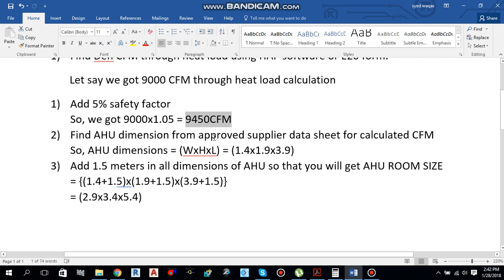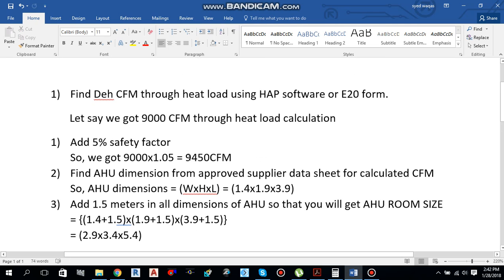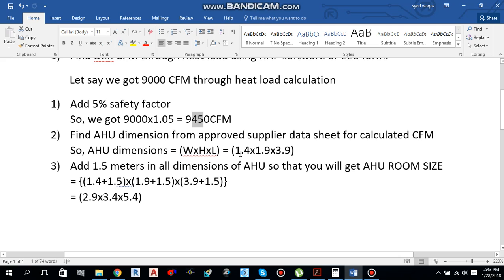As you can see, the AHU selected from the approved supply data sheet for our calculated CFM of 9450 CFM has width 1.4 m, height 1.9 m, and length 3.9 m. If we add 1.5 meters to all dimensions of the air handling unit, we get the room size. Adding 1.5 m to the width, 1.5 m to the height, and 1.5 m to the length gives us a total AHU room size of: width 2.9 m, height 3.4 m, and length 5.4 m.